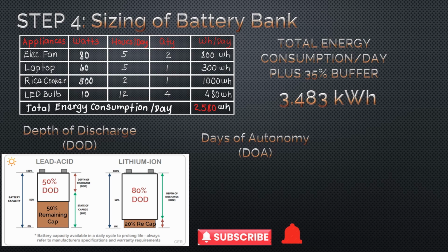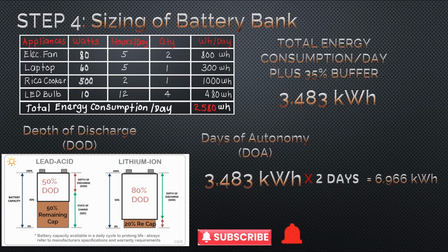Talking about days of autonomy, this is the capacity of the battery to supply the loads independently, that is without solar and grid, considering the battery bank is fully charged. To demonstrate it in our example, we already knew that 3.483 kWh is the amount of energy in a day to be supplied by battery or solar.